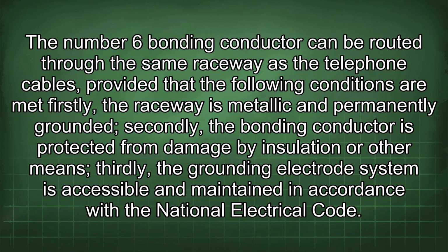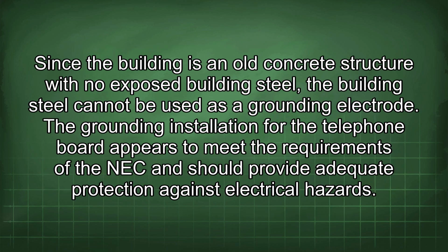conditions are met. Firstly, the raceway is metallic and permanently grounded. Secondly, the bonding conductor is protected from damage by insulation or other means. Thirdly, the grounding electrode system is accessible and maintained in accordance with the National Electrical Code. Since the building is an old concrete structure with no exposed building steel, the building steel cannot be used as a grounding electrode. The grounding installation for the telephone board appears to meet the requirements of the NEC and should provide adequate protection against electrical hazards.